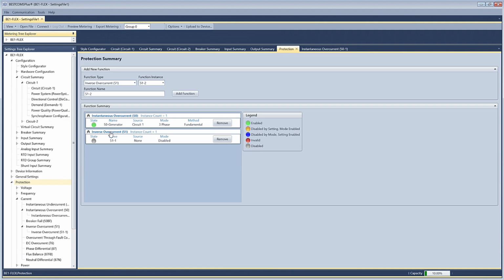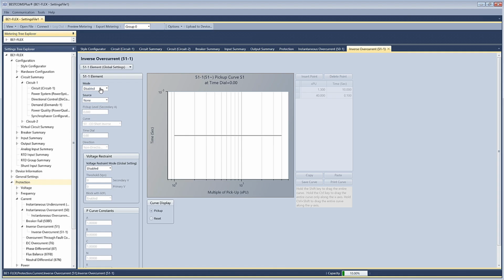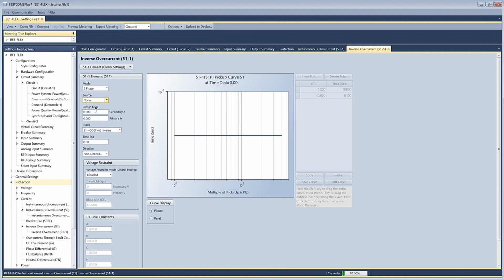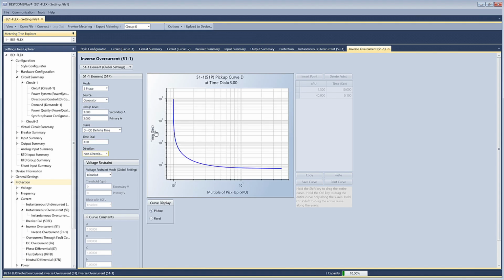So next I'm going to go down to my protection again to get back to my summary, click 51-1. Same thing, check my source, give it a pickup level, give it a time curve. You can select any time curve you want. It even gives you a nice graphic on the side. Give it a time dial, things that you're going to have calculated with coordination settings in this particular example. One of the things I do mention is if you hover over the graph, it does actually show you the calculated values. So especially from a troubleshooting perspective or even just a sanity check, it's a nice little way to see, is this the curve that I wanted to operate on?